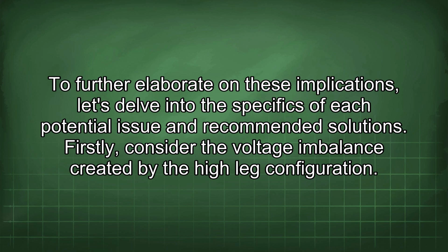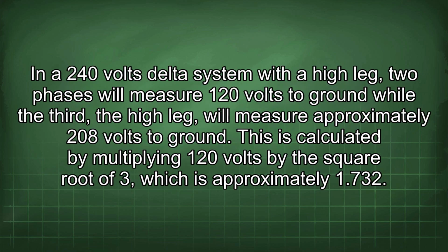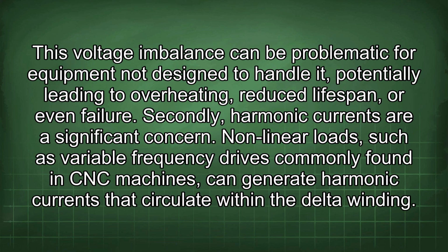Firstly, consider the voltage imbalance created by the high leg configuration. In a 240 volts delta system with the high leg, 2 phases will measure 120 volts to ground, while the third, the high leg, will measure approximately 208 volts to ground. This is calculated by multiplying 120 volts by the square root of 3, which is approximately 1.732. This voltage imbalance can be problematic for equipment not designed to handle it, potentially leading to overheating, reduced lifespan, or even failure. Secondly, harmonic currents are a significant concern.